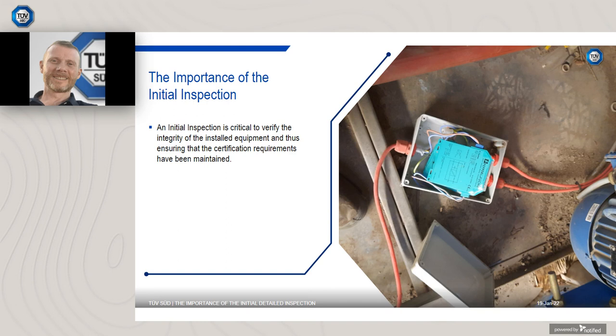An initial inspection is critical to verify the integrity of the installed equipment, and thus ensure the certification requirements have been maintained. Suppliers spend thousands on certifying their products to ensure safety and compliance. If the installation is poor, this can potentially be undone. Certification could be compromised based on the quality of the installation, and that becomes the onus of the owner.